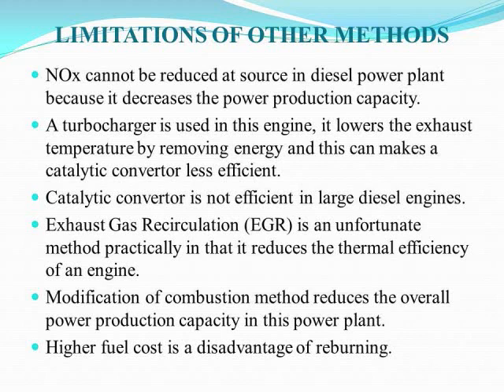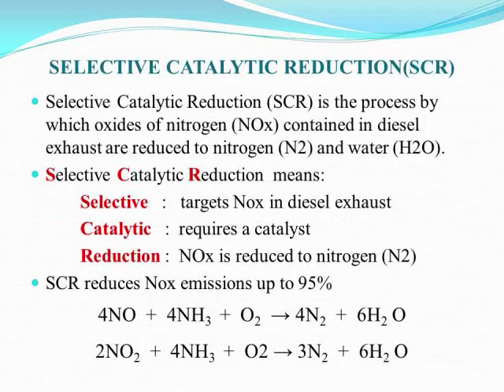The limitations of other methods are as follows: NOx cannot be reduced at source in a diesel power plant because it decreases power production capacity — generally 200 megawatt. Exhaust gas recirculation can be installed but reduces thermal efficiency of the engine. Modification of combustion also reduces overall power production capacity.